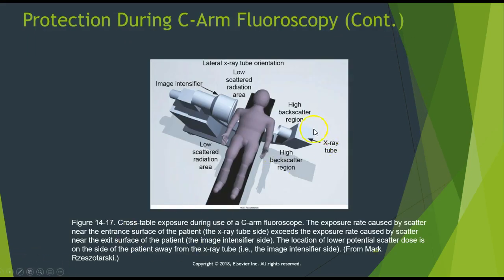So for instance, the X-ray tube here is on the side of the patient. Say you're doing a shoulder or humerus, or a total, and they want to see a picture, and you bring in the C-arm. You put the X-ray tube here. You're going to have the highest level of scatter next to this X-ray tube where it hits the patient. You're going to have the lowest level of scatter next to the image intensifier.